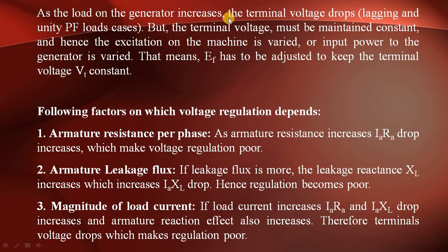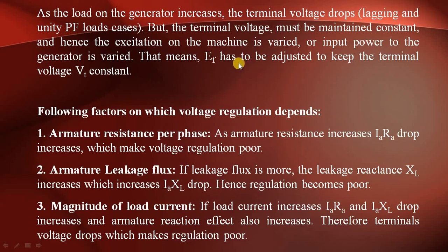As the load on the generator increases, the terminal voltage drops for lagging and unity power factor loads. Since the terminal voltage must be maintained constant, the excitation of the machine is varied — that is, EF is adjusted to keep the terminal voltage VT constant. This is the voltage regulation of the alternator.